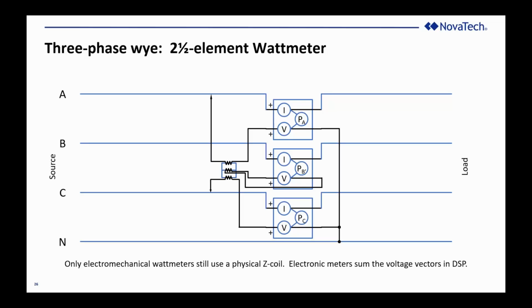It doesn't have to connect to the B-phase voltage because you're presuming the balance and it's determining that voltage internally, but the real only savings is on the PT. So, for legacy purposes, and because we do still see them once in a while, we still manufacture meters.